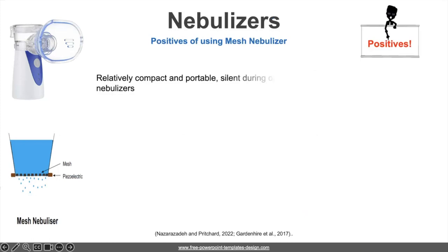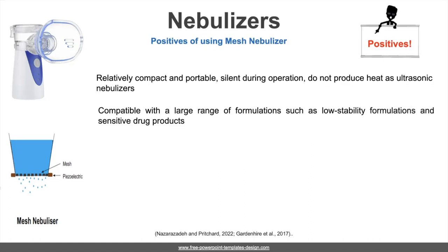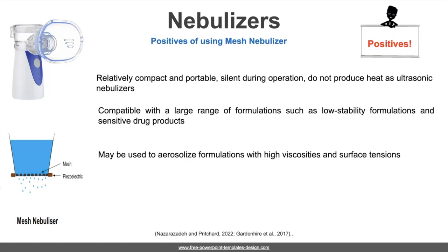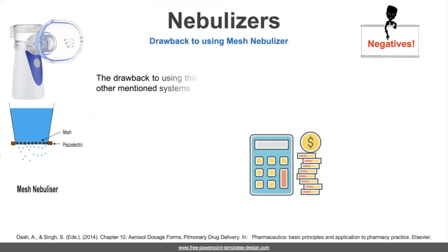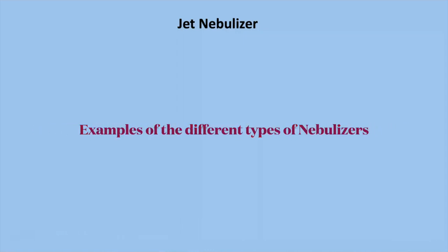The merits of mesh nebulizers include being relatively compact and portable, silent during operation, and not producing heat as ultrasonic nebulizers do. As such, they are compatible with a large range of formulations, including low-stability formulations and sensitive drug products. They are also able to aerosolize formulations with high viscosities and surface tensions, which is not possible with previously mentioned nebulizers. The drawback is cost, which is typically high in comparison to the other systems. Here are some examples of the nebulizers just discussed.